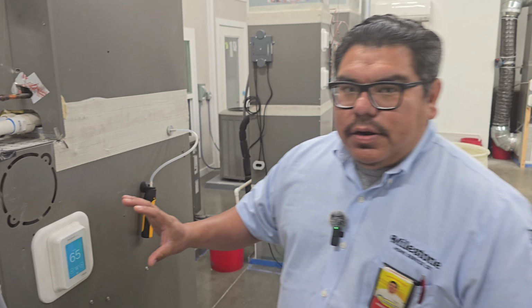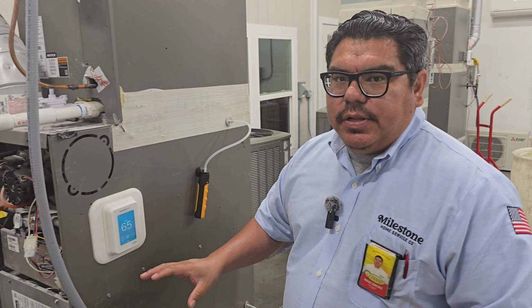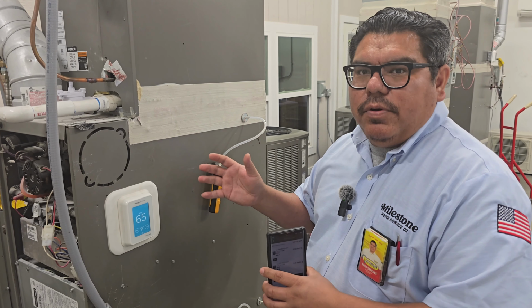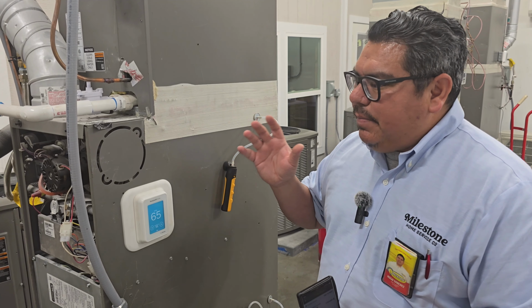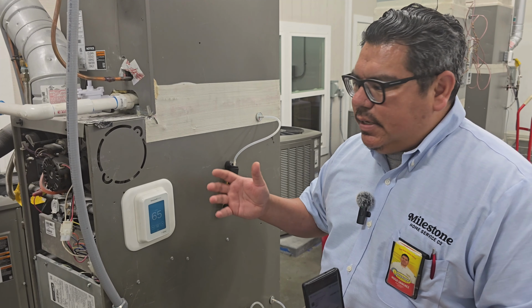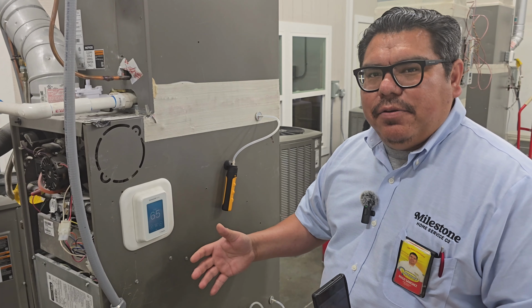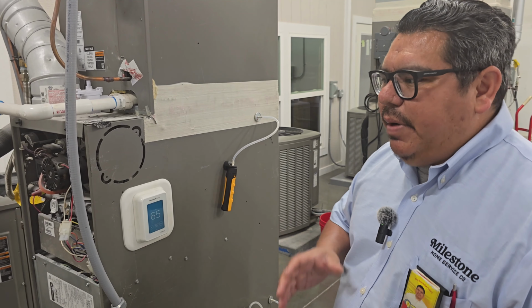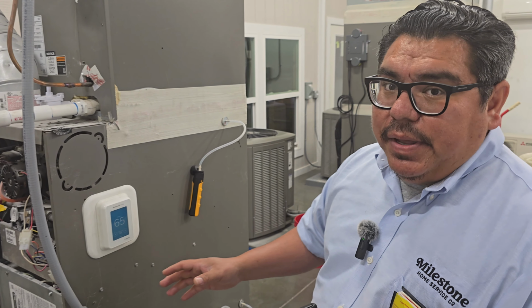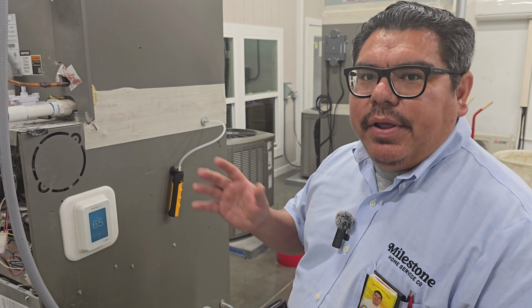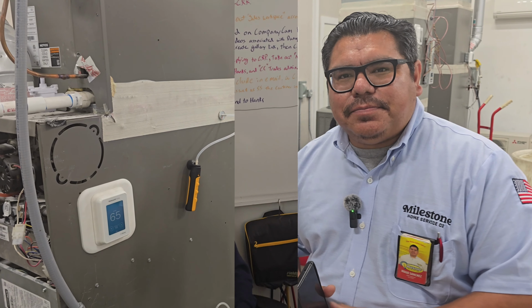And if you're working on a system that's a 2-ton, you want to make sure that your CFMs are going with that 2-ton, right? Same thing with any unit that's not going to tell you what the CFMs are. Look at the manual and make sure that you're comparing the blower speeds to the static pressure. That way it'll give you your CFMs, and that's the way you'll get your proper readings.